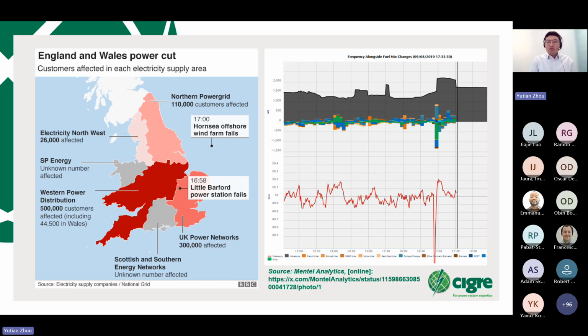But this led to an impact on local distribution networks with initial disconnection of 150 megawatts of distributed generation, because they have to be tripped off due to a safety mechanism known as the vector shift protection. And following that, the voltage control system at the Hornsea 1 offshore wind farm did not respond to the impact of the fault on the transmission system as expected and became unstable. And that led to a rapid reduction of its power generation. In essence, it was reduced from around 800 megawatts down to 62 megawatts. So that is over 700 megawatts of reduction.